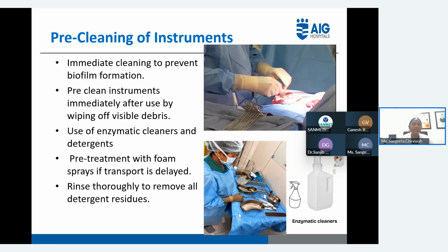The first step is immediate cleaning to prevent biofilm formation. Pre-clean the instruments immediately after use by wiping off visible debris, as we can see in this video, once they are received at the table. Use enzymatic cleaners and detergents, pre-treat with foam spray if transport is delayed, and rinse thoroughly to remove all detergent and residues.